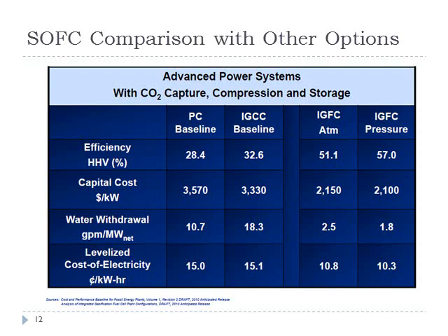For example, here are a couple of cases in which you have a pulverized coal plant, that's a PC, then an integrated gasification combined cycle power plant, which is the next one. The next couple are when you have gasification, you turn coal into a syngas, and send that syngas not to a gas turbine, but to a fuel cell. And here you can see the general efficiencies, the amount of electricity divided by the higher heating value of the coal, some of the capital costs in dollars per kilowatt net AC, and how much water is used.